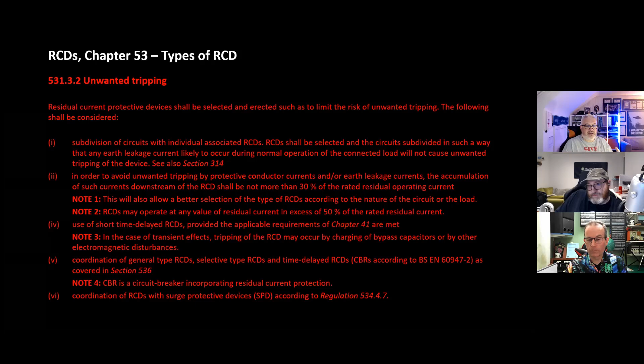It then says this will allow better selection of RCD due to the nature of the load. RCDs may operate at a value of residual current in excess of 50%. So you can use time delayed, you have to do coordination, selectivity, etc., and coordinate them with surge protection devices as well. So that's the existing reg. In the new bit, and I've just kept it in white so that I don't go blind, they have added an additional part, and this is what we kind of missed yesterday. So you can still have all of the existing criteria, but there's an additional line that says the use of RCBOs for individual final circuits in domestic installations.